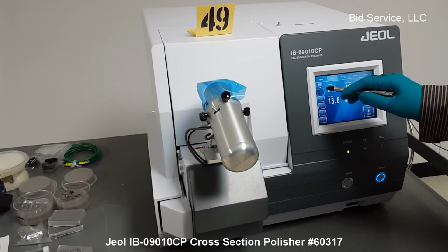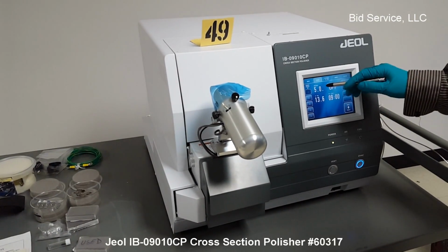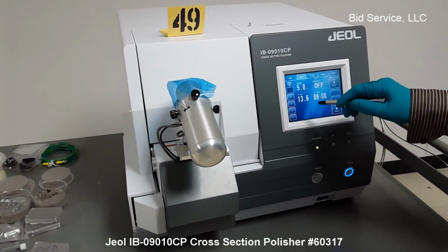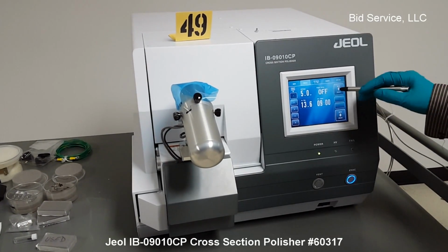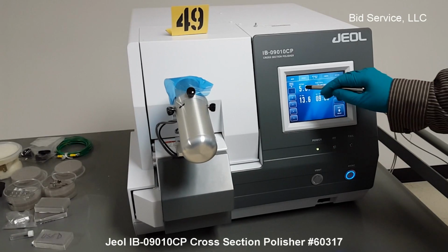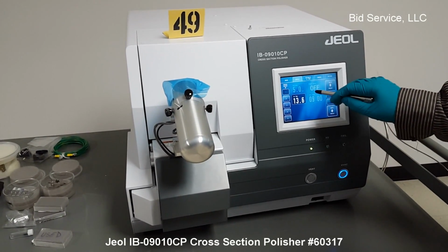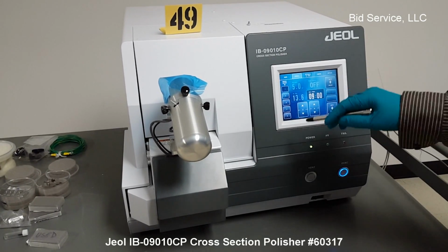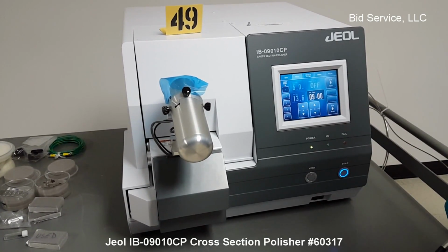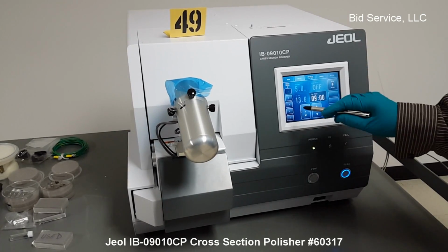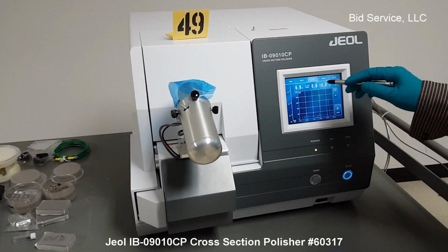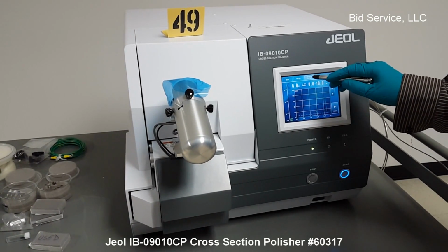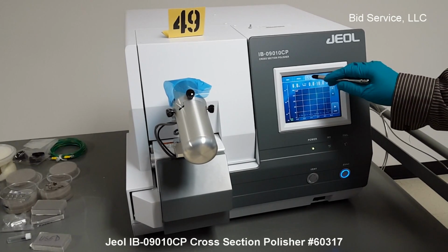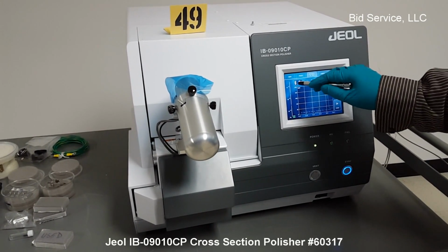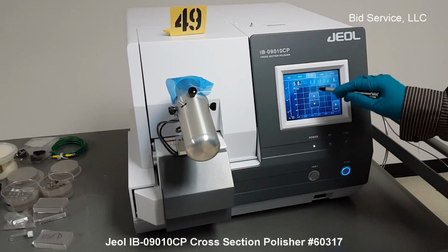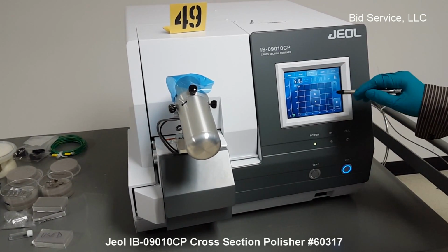There's a provision for preset parameter setting, like high voltage in kilovolts, gas flow value, and timer. All these values can be preset and saved in the memory. There are 5 pre-selections available. And also, to optimize the argon gas flow, there's a menu item. Any desired kilovolts can be selected, and high voltage, say at 5 kilovolts.